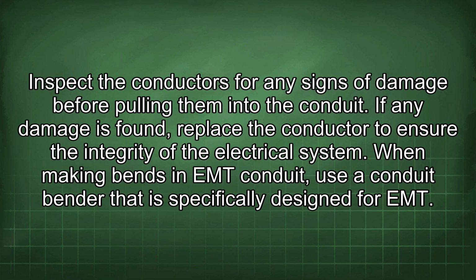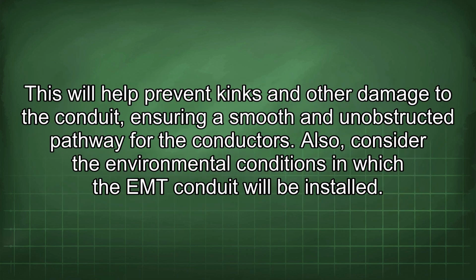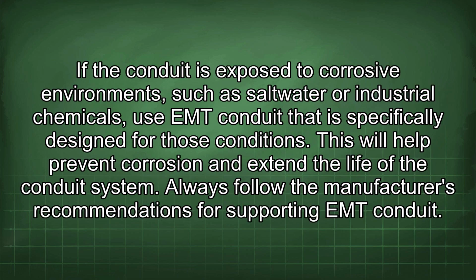When making bends in EMT conduit, use a conduit bender that is specifically designed for EMT. This will help prevent kinks and other damage to the conduit, ensuring a smooth and unobstructed pathway for the conductors. Also, consider the environmental conditions in which the EMT conduit will be installed. If the conduit is exposed to corrosive environments such as saltwater or industrial chemicals, use EMT conduit that is specifically designed for those conditions. This will help prevent corrosion and extend the life of the conduit system. Always follow the manufacturer's recommendations for supporting EMT conduit.